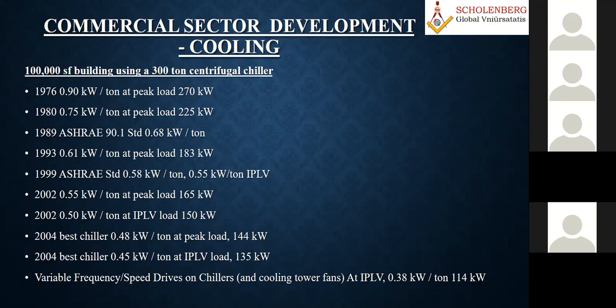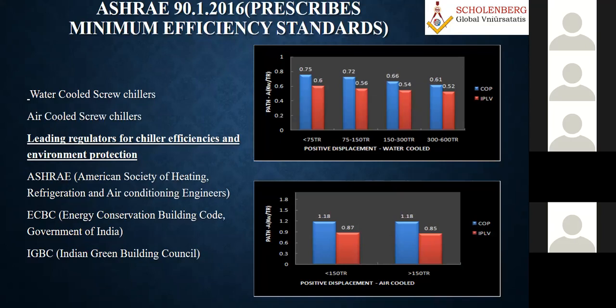maybe 0.75 or 0.73. Even when we selected our chiller here, we have taken 0.72 or 0.73. That's what they have quoted us. So these are all for the various types of water cooled chillers and air cooled chillers, and how the development started with ASHRAE as well as with the Energy Conservation Building Code, Government of India, both. So these are some of the standards with the COP as well as with the integrated part load value also.